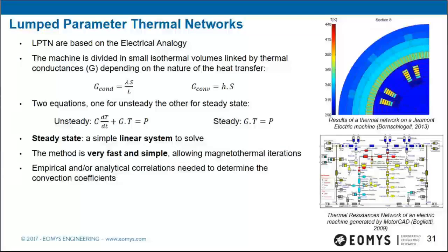Lumped parameter thermal networks (LPTN) are based on the electrical analogy: the machine is divided into small isothermal volumes linked by thermal conductances depending on the nature of the heat transfer — conductive conductance and convective conductance. In steady state, the equation becomes a simple linear system, easy to solve. LPTN is very fast and simple to implement. However, empirical and analytical correlations are needed to determine the convective coefficients H.